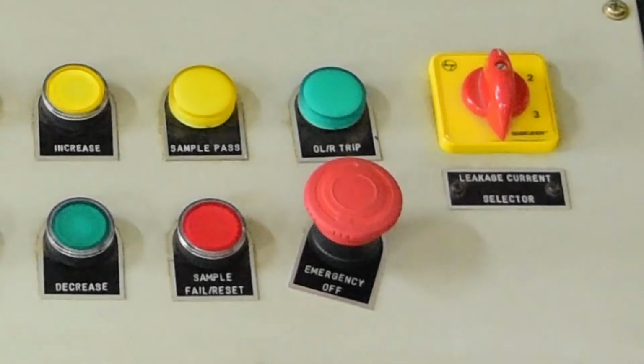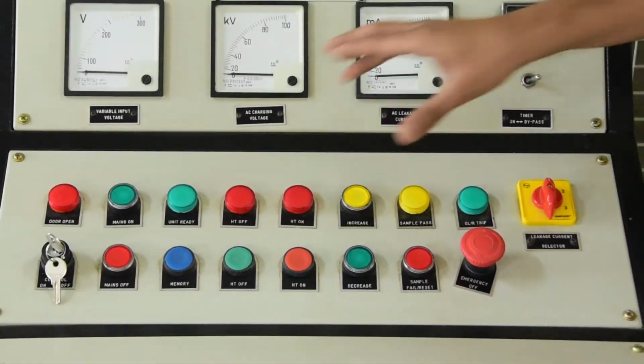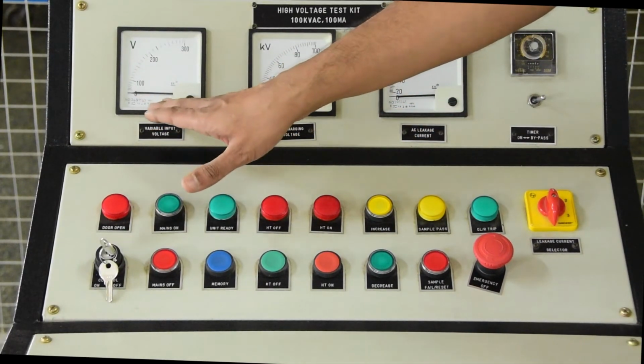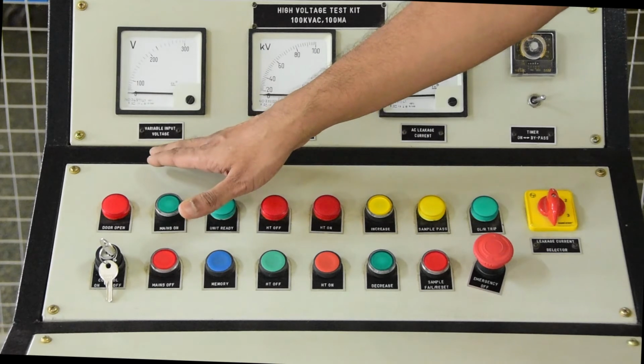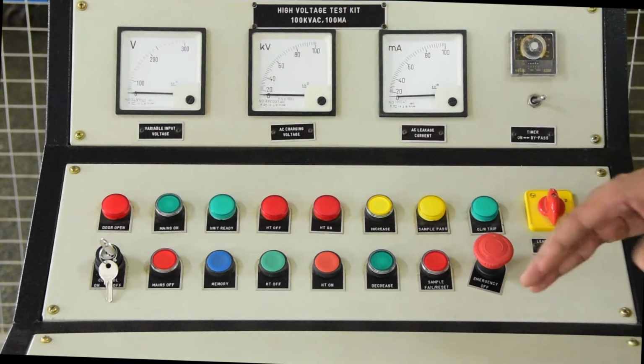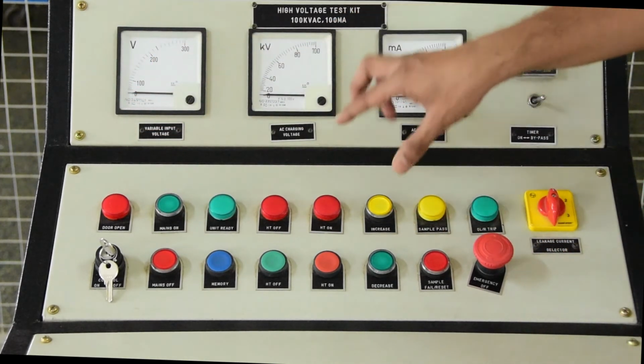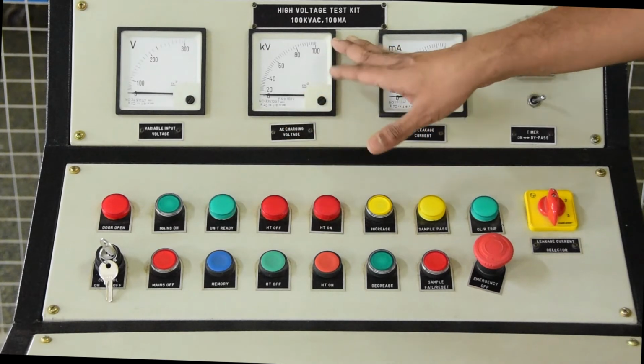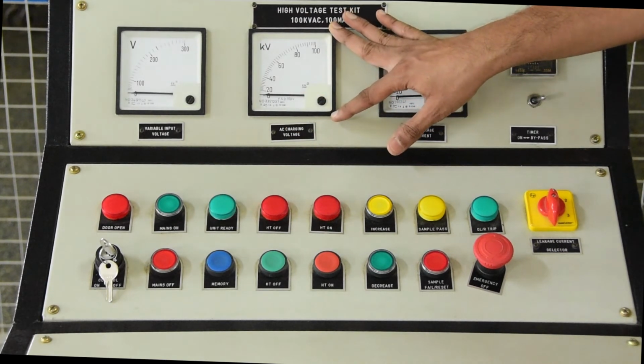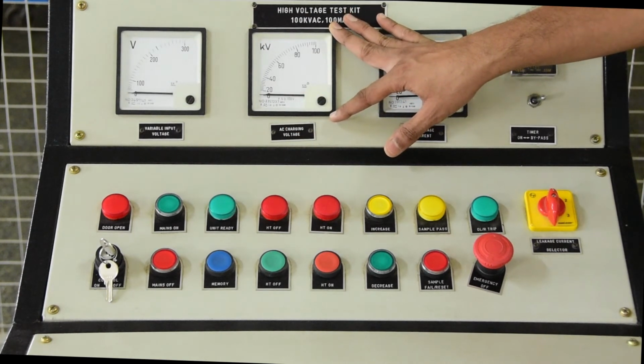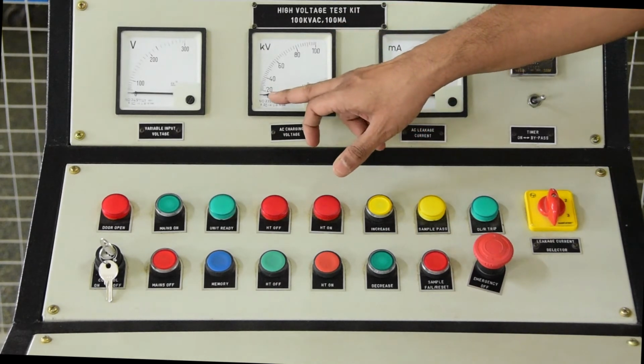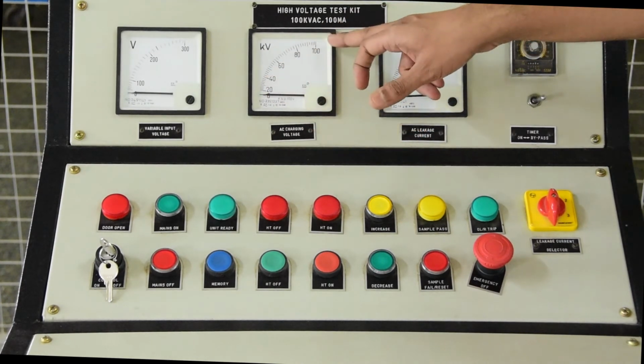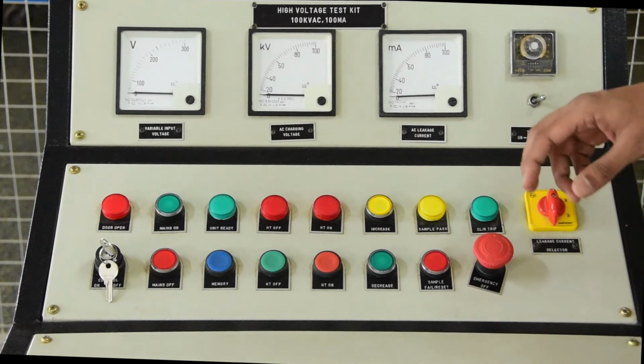The upper level indication is again very similar to the solid insulation tester. On the left hand side is the input voltage, a variable input voltage shown from 0 to 300 volts single phase, and the second one is the output voltage available across the cascade transformer. It is showing from 0 to 100 kV, so a maximum of 100 kV can be produced.